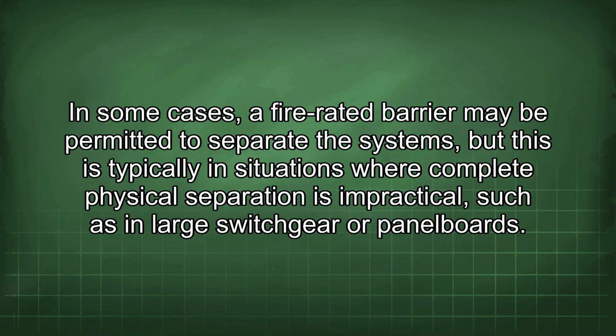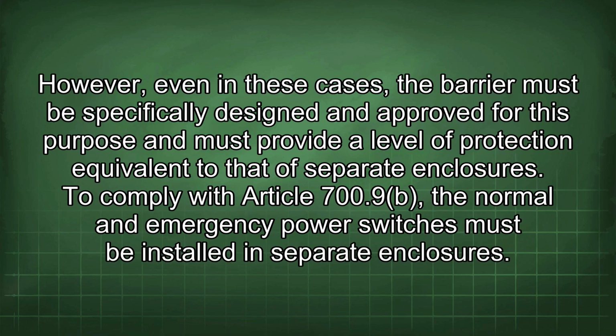In some cases, a fire-rated barrier may be permitted to separate the systems, but this is typically in situations where complete physical separation is impractical, such as in large switchgear or panel boards. However, even in these cases, the barrier must be specifically designed and approved for this purpose and must provide a level of protection equivalent to that of separate enclosures. To comply with Article 700.9, the normal and emergency power switches must be installed in separate enclosures.